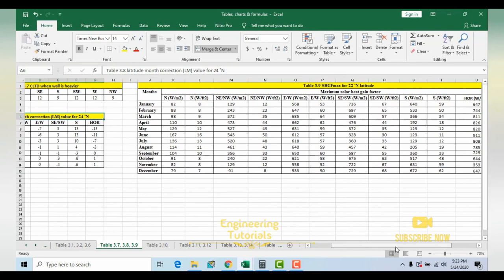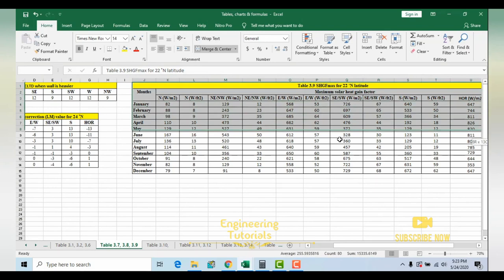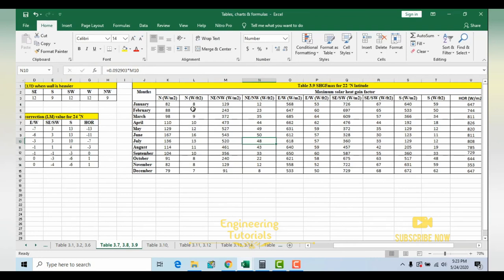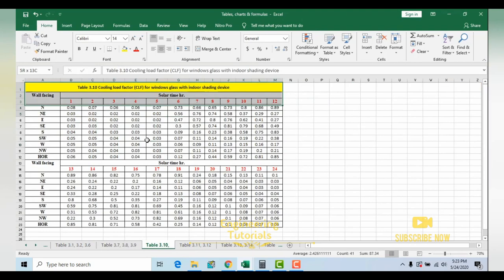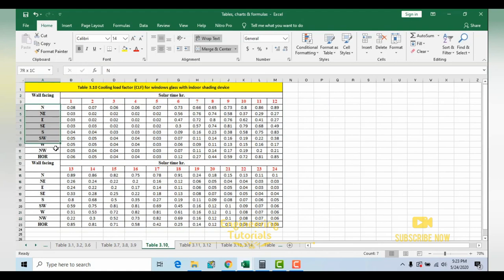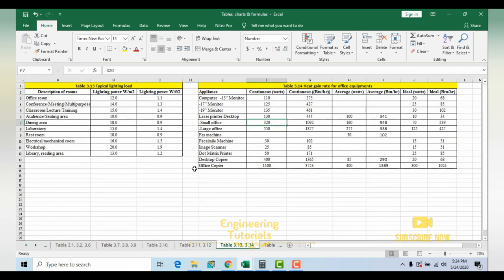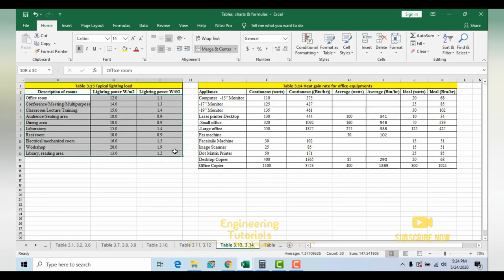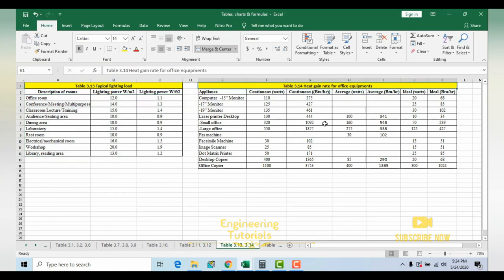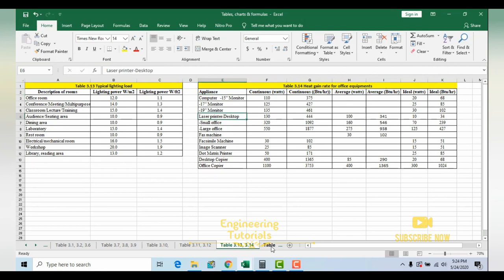The solar heat gain factor (SHGF maximum) table gives maximum solar heat gain for glass for different months and directions. The cooling load factor table (Table 3.10) gives factors for different times and directions. We also have a table for heat gain from occupants (sensible and latent heat per person), a lighting load table for different building types, heat gain from office equipment, and infiltration load calculation using air changes per hour. Ventilation rate per person is given in cubic meter per minute per person.